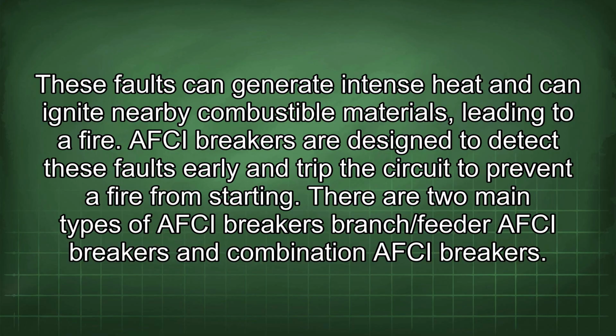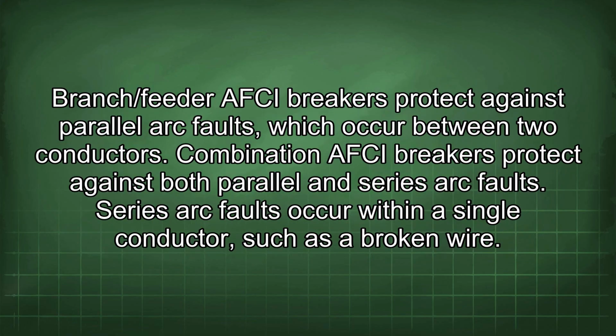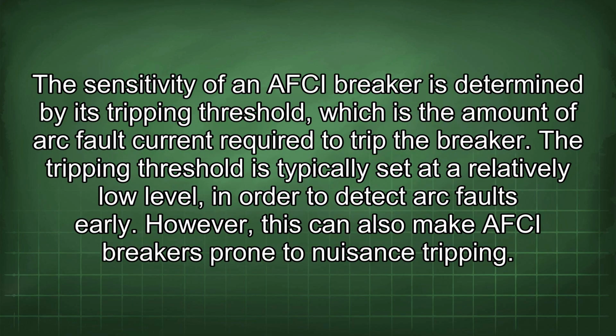There are two main types of AFCI breakers: branch/feeder AFCI breakers and combination AFCI breakers. Branch/feeder AFCI breakers protect against parallel arc faults, which occur between two conductors. Combination AFCI breakers protect against both parallel and series arc faults. Series arc faults occur within a single conductor, such as a broken wire. The sensitivity of an AFCI breaker is determined by its tripping threshold, which is the amount of arc fault current required to trip the breaker.